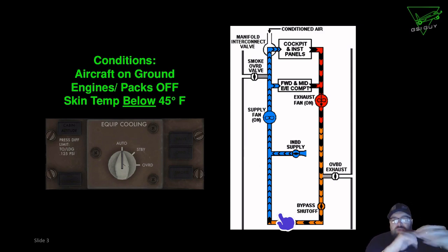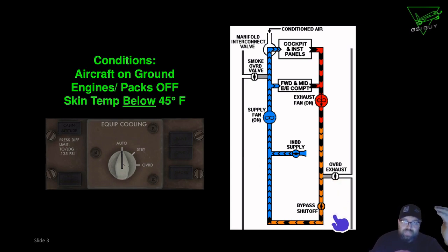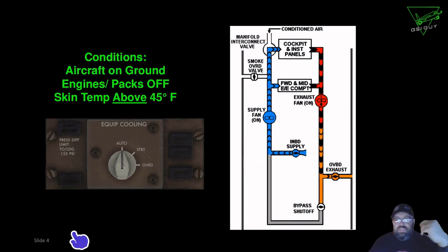Whenever the skin of the aircraft is below 45 degrees Fahrenheit, this bypass shutoff is open. If it's open, it allows air to come through that skin heat exchanger and back into the system, because it's efficient enough to cool the air down enough to go back into the system without making it overheat.